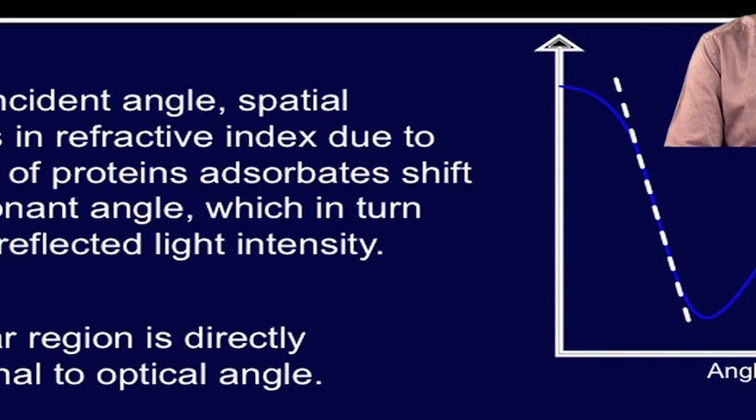In this slide, a setup of SPR imaging is shown. The configuration illustrates that light from a collimated polychromatic source passes through a polarizer and impinges on the prism or gold interface at a specific angle of incidence. As we can see here, there is a gold surface, the prism, and the light source. Now, the reflected light passes through the narrow band interference filter and is detected by the CCD camera. Therefore, at a fixed incident angle, the spatial variations in refractive index due to the presence of protein or other molecule adsorbates shift the local resonant angle, which in turn changes the reflected light intensity.